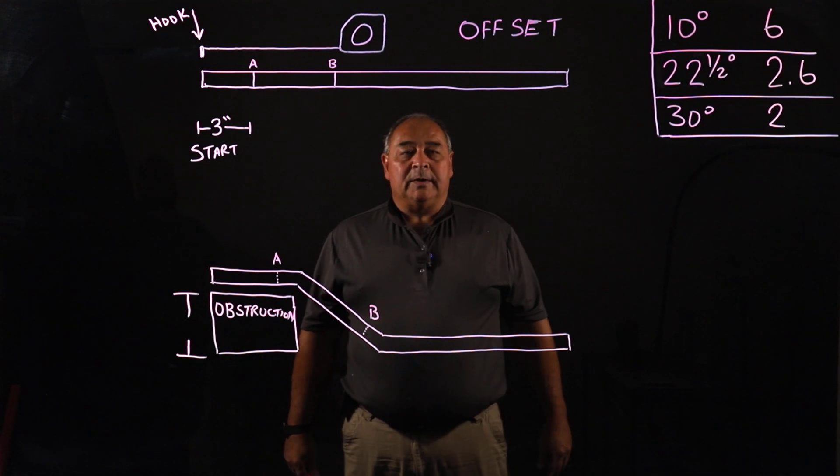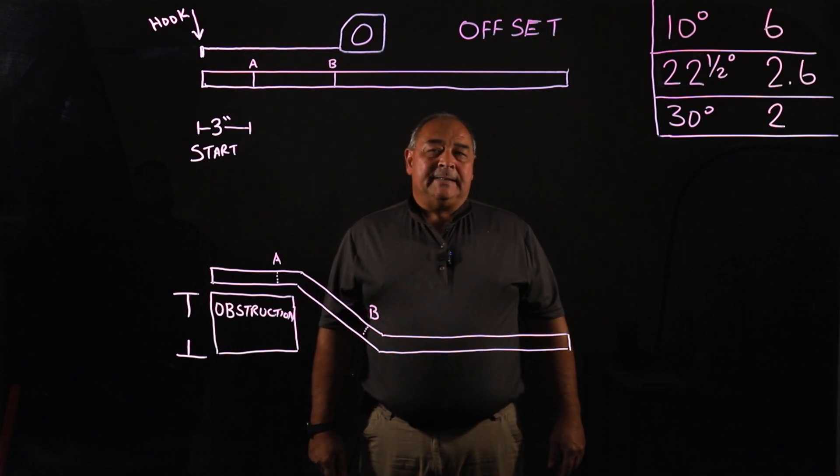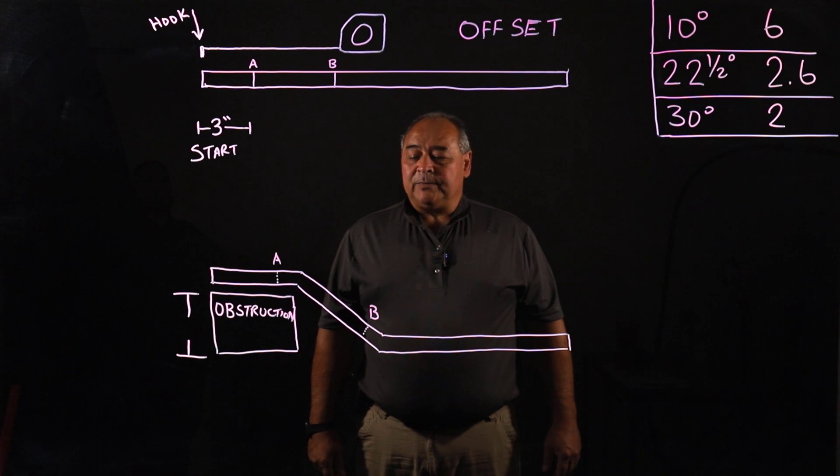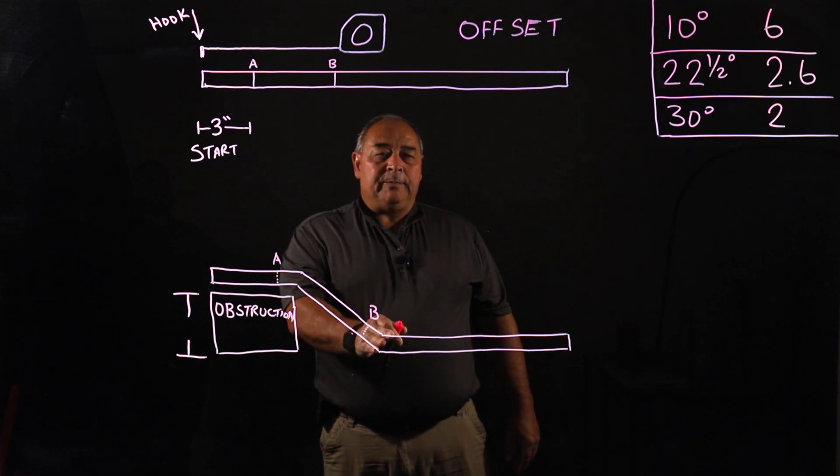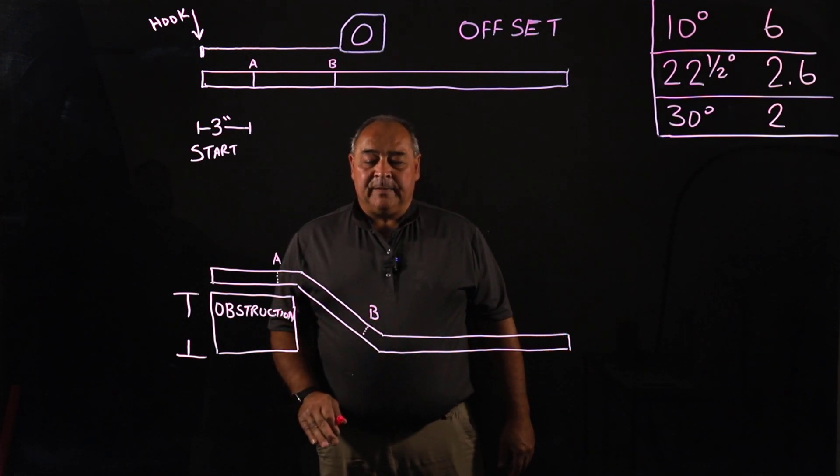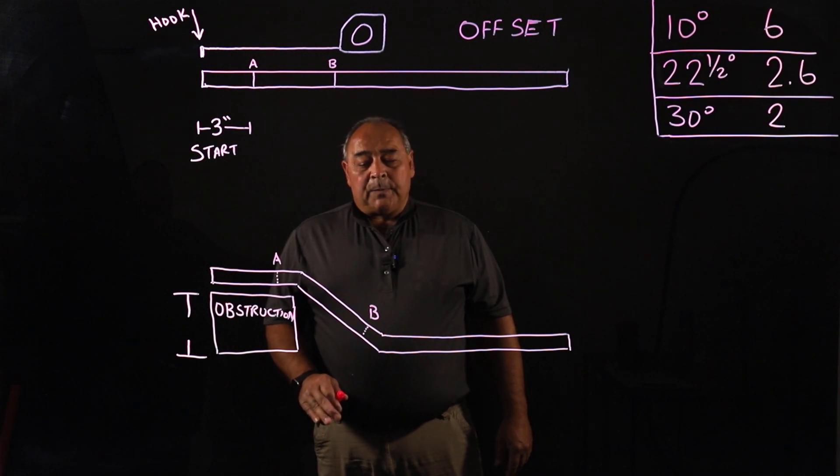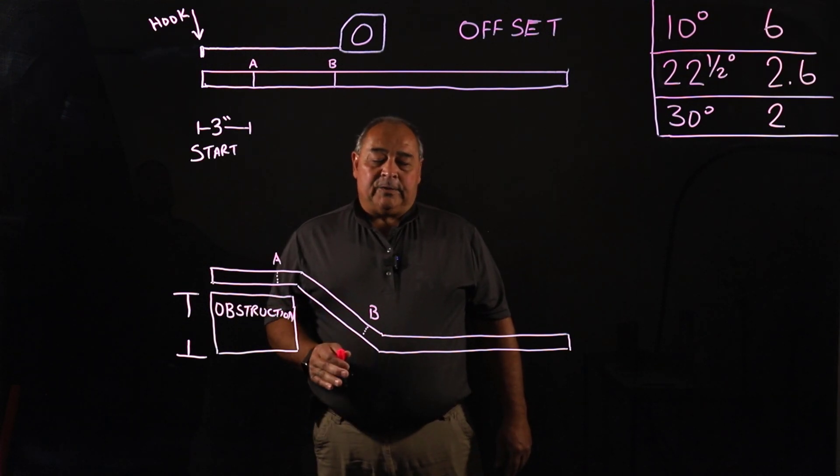We have suggestions and our goal, once we get to the three inch obstruction and beyond, we want to stay around a 30 degree bend. The reason why is two 30 degree bends equals 60 degrees. Two 45 degree bends equals 90 degrees.